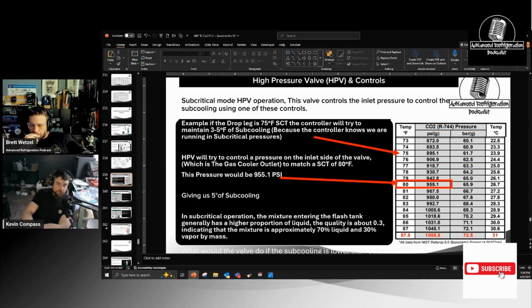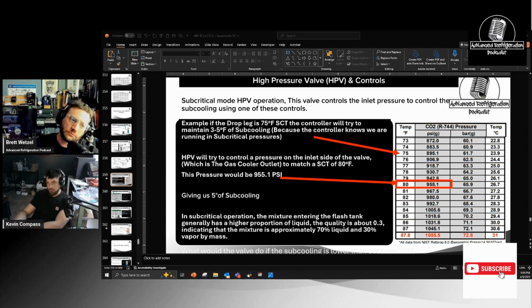It may get so warm from that convection and that radiant heat that when it goes to start, it's going to start that HPV up at a 1,400 pound set point. When it does that, the HPV is not open enough to have enough flow without banging on compressors, because it's going to start banging them off on high head instantly, since the set point's too high right away, and it just murders the compressors. And it won't restart until you get refrigerant flow going through the gas cooler to cool it down. And it'll drop, but it may bang on and off for a half hour to an hour.